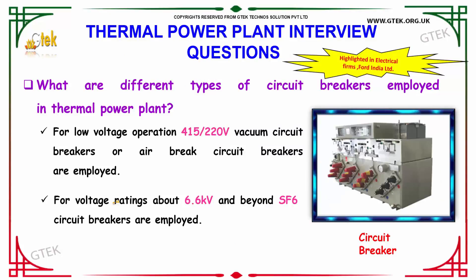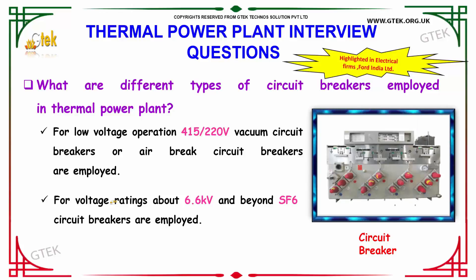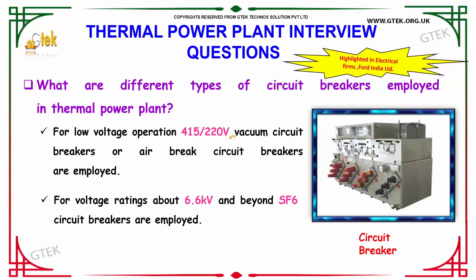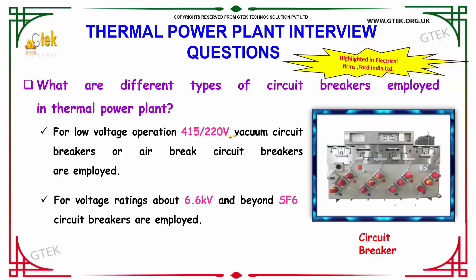What are the different types of circuit breakers employed in a thermal power plant? For low voltage operation in the power plant, 415–220V vacuum circuit breakers or air break circuit breakers are employed. For voltage ratings of 6.6kV and beyond, SF6 circuit breakers are employed.